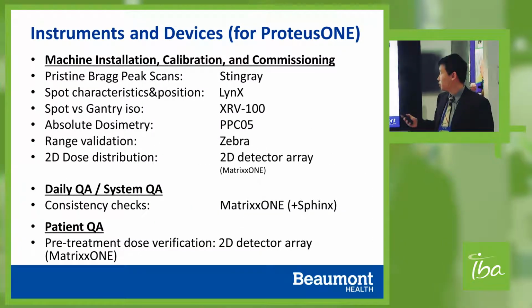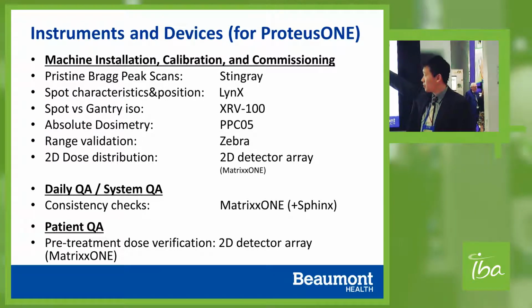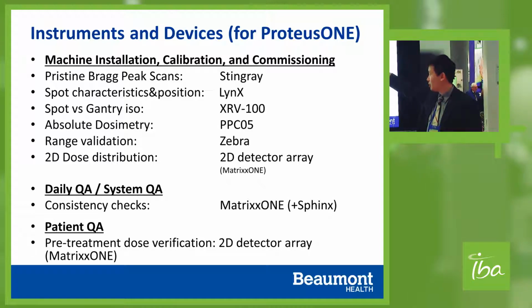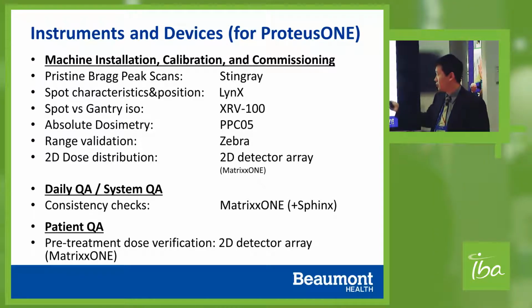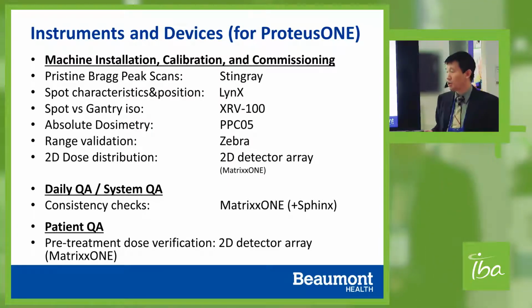So here's the experiment setup we use in the bunker. From the top to down: Stingray for the Bragg peak chamber, Lynx just for spot characteristics and position check, and isocentricity using XRV 100, and absolute dosimetry with the PPC05, Zebra for the range verification, and the Matrixx 1 for the 2D detector. Daily QA is using Matrixx 1 as well. So this is the minimum requirement for the dosimetry equipment that you need for commissioning the PBS system.